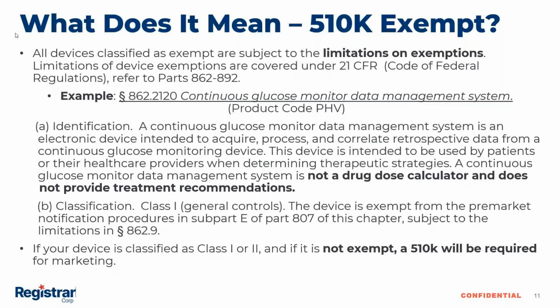So that is clearly the limit. If your system is used to calculate the dosage, or gives you treatment recommendations, then that is not the product code you should use. And hopefully that gives you an idea about what is called the limitations of a 510K.